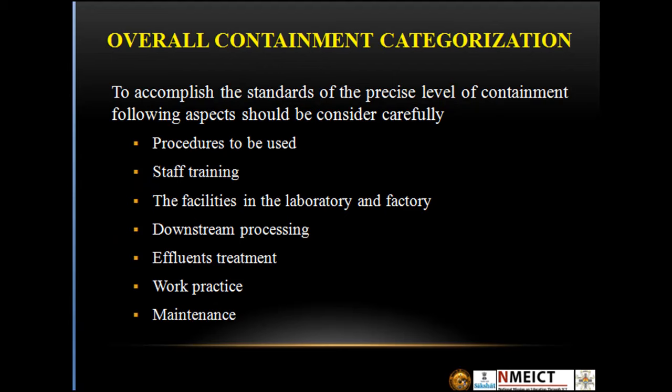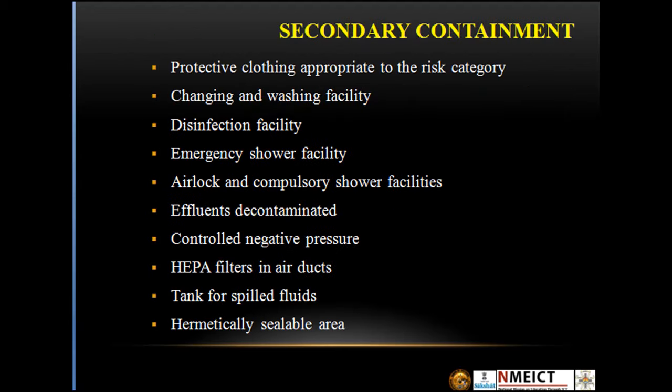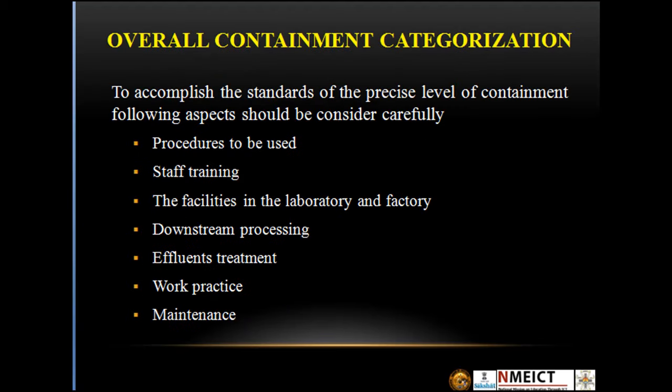Secondary containment includes: protective clothing appropriate to the risk category, changing and washing facilities, disinfection facilities, emergency shower facilities, air lock and compulsory shower facilities, effluent decontamination, controlled negative pressure, HEPA filters, HEPA filters in air ducts, tanks for spilled fluid, and hermetically sealable areas.